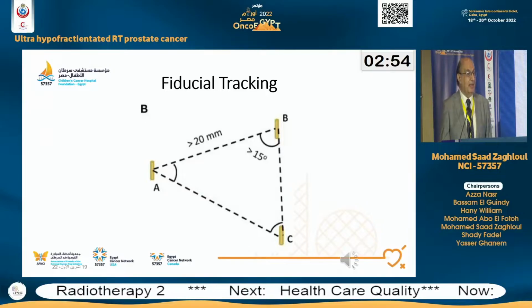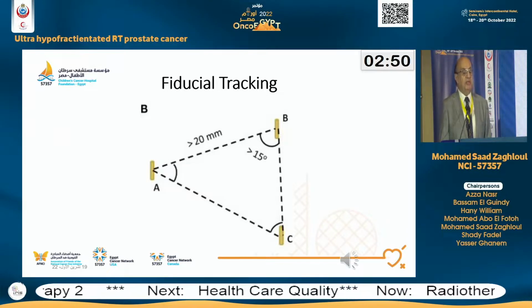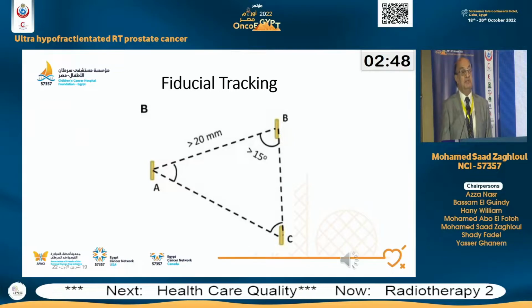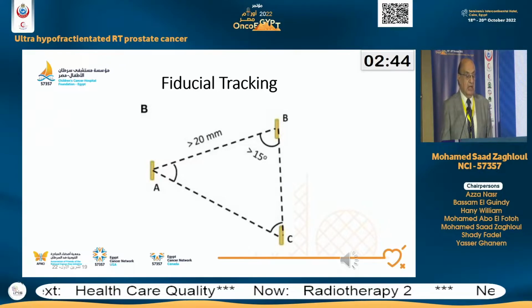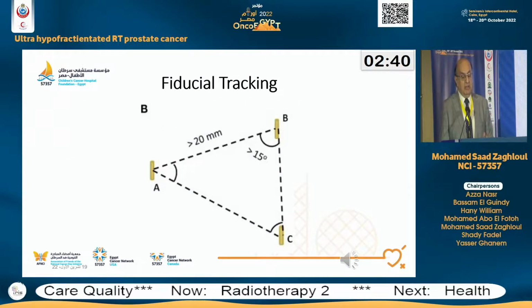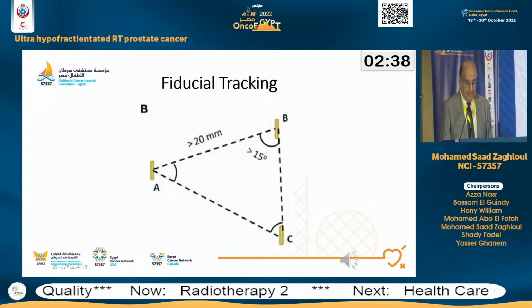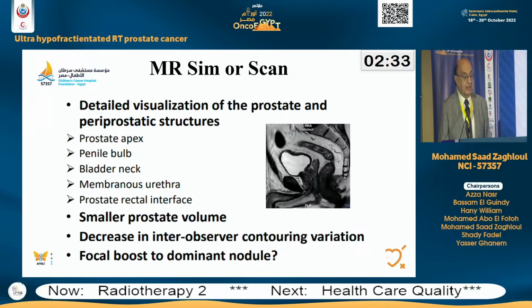The fiducials have to be at least 20 millimeters apart from each other, and we have to have the angle more than 15 degrees in order to get this done correctly.